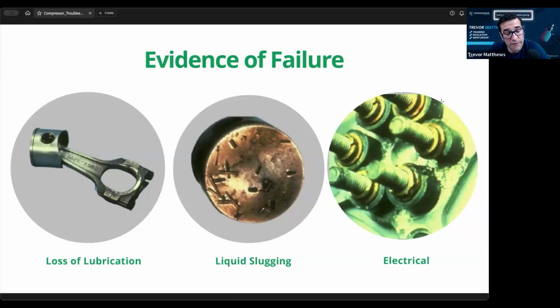Because like I said, I've torn down thousands of compressors, and you look at the model number and the serial number, and you can tell this has been replaced already. How many times has it been replaced? This is the third time. Why has the compressor been replaced 3 times? You know what I mean? Check that oil level. What is the oil level? Was there oil in the compressor? What color is the oil? Why? You know what I mean? These are things that you need to be thinking about.